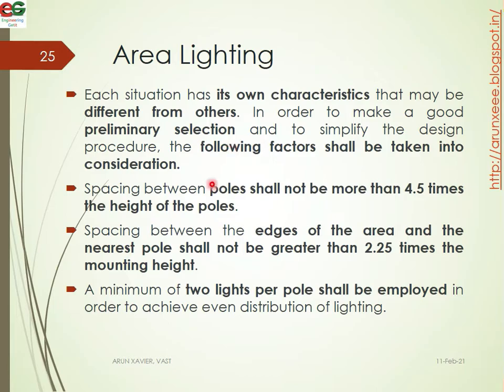Spacing between the poles: the poles shall not be spaced more than 4.5 times the height of the pole. Spacing between the edges of the area and the nearest pole shall not be greater than 2.25 times the mounting height.